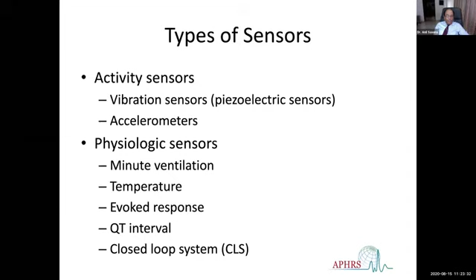So this is the piezoelectric crystal, which is inside the body, and it senses the vibration when the muscular activity or the body activity takes place. This is the accelerometer, which senses the movement of the body. And then we have minute ventilation, also used commonly in some pacemakers, which measures the impedance between the pacemaker body and the lead tip. So thoracic impedance. What happens is it can count the respiratory rate. You see in ICUs, the monitors can count the respiratory rate, and that is by measuring the phasic changes in the thoracic impedance.